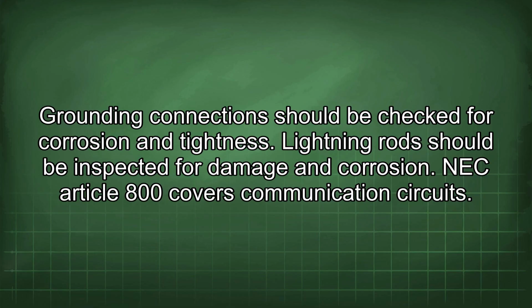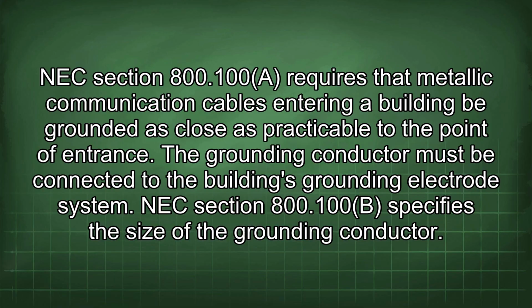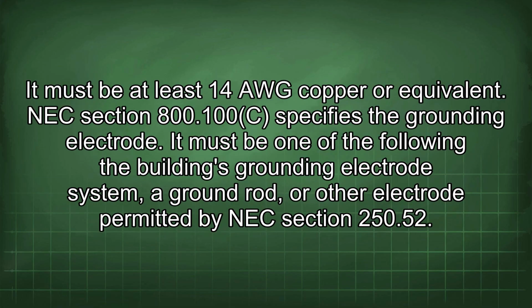NEC Article 800 covers communication circuits. NEC Section 800.100 requires that metallic communication cables entering a building be grounded as close as practicable to the point of entrance. The grounding conductor must be connected to the building's grounding electrode system. NEC section 800.100(B) specifies the size of the grounding conductor. It must be at least 14 AWG copper or equivalent.